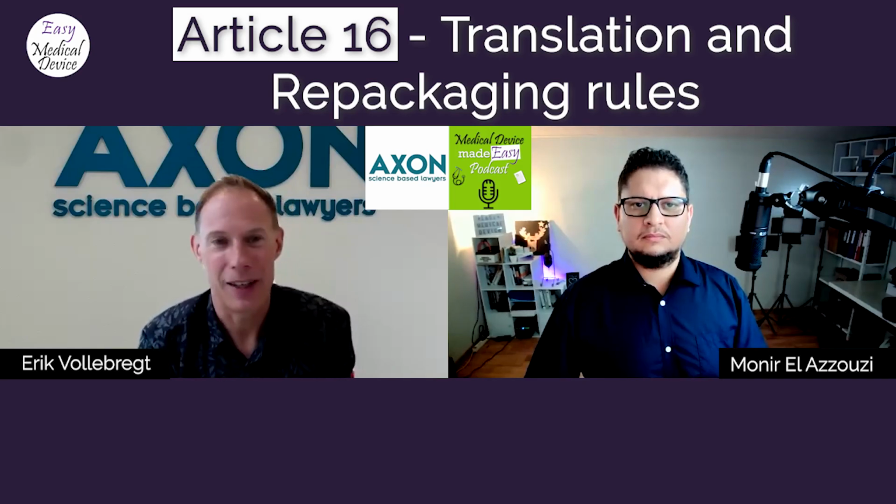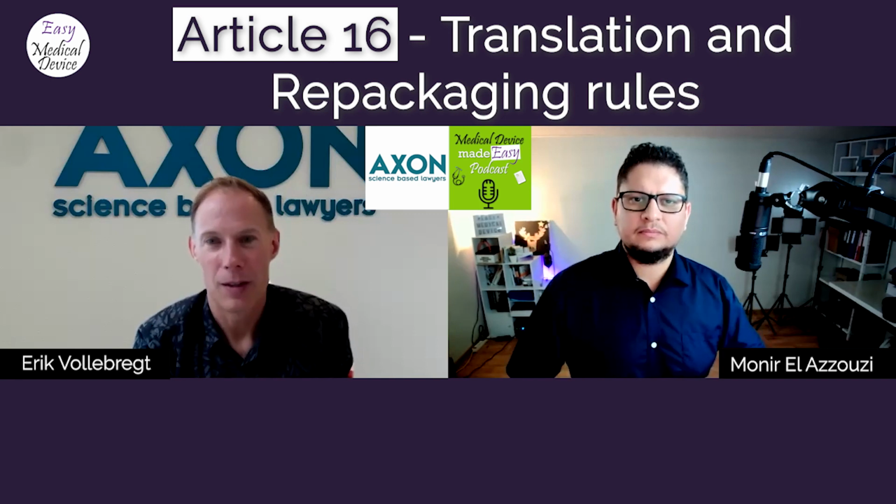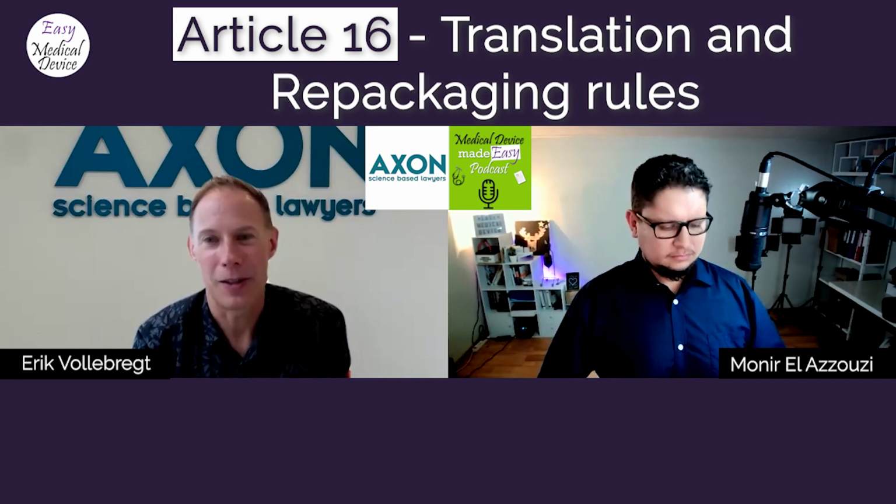But now we had the MDR and the IVDR enter into force, and they provide for a much more specific regime that says there are a number of criteria that you have to meet as a distributor. First of all, if you engage in repacking and translation, you must not be seen as a manufacturer. And if you are not seen as a manufacturer, then there is still a list of criteria that you have to meet. For example, you need to have a quality system for the activity.